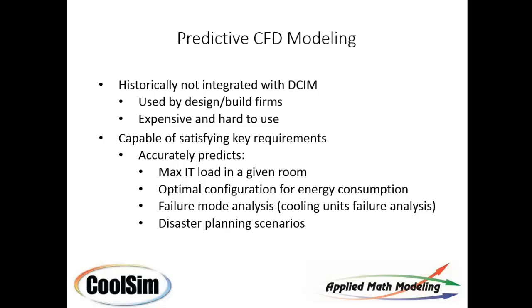The issue there, however, is that they don't know all the information at that point in time about what's going to be in the room. So they have to build it for a max load configuration, which is often much higher than will be seen for a very long time. So the data centers are often running below capacity, certainly below their thermal capacity by quite a wide margin, which makes them tend to run quite inefficient.